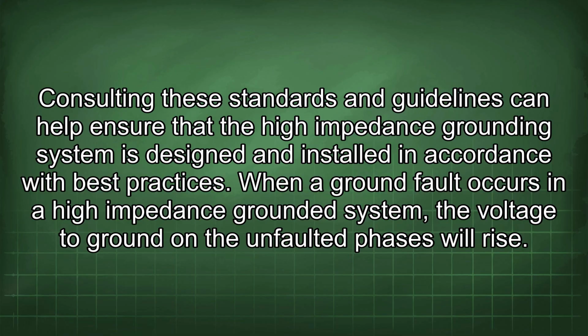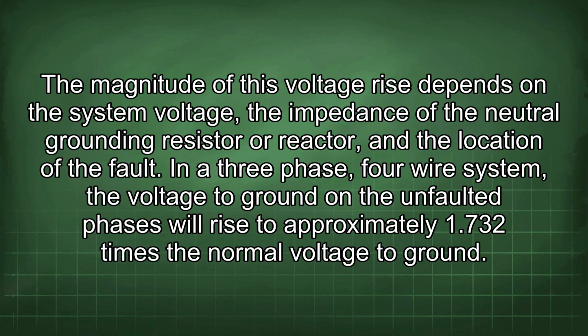When a ground fault occurs in a high-impedance grounded system, the voltage to ground on the unfaulted phases will rise. The magnitude of this voltage rise depends on the system voltage, the impedance of the neutral grounding resistor or reactor, and the location of the fault.